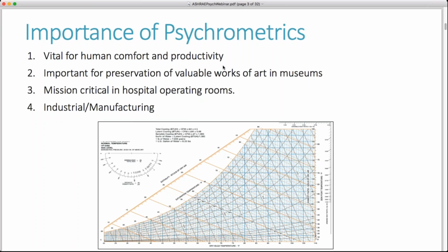Therefore, using psychrometrics, it's possible to design systems with the proper humidity ratio to eliminate that condensation. Finally, many industrial and manufacturing companies use chilled water to remove heat from various manufacturing processes. As the air or process is cooled below the ambient dew point, condensation can occur, similar to what could happen in a hospital OR.